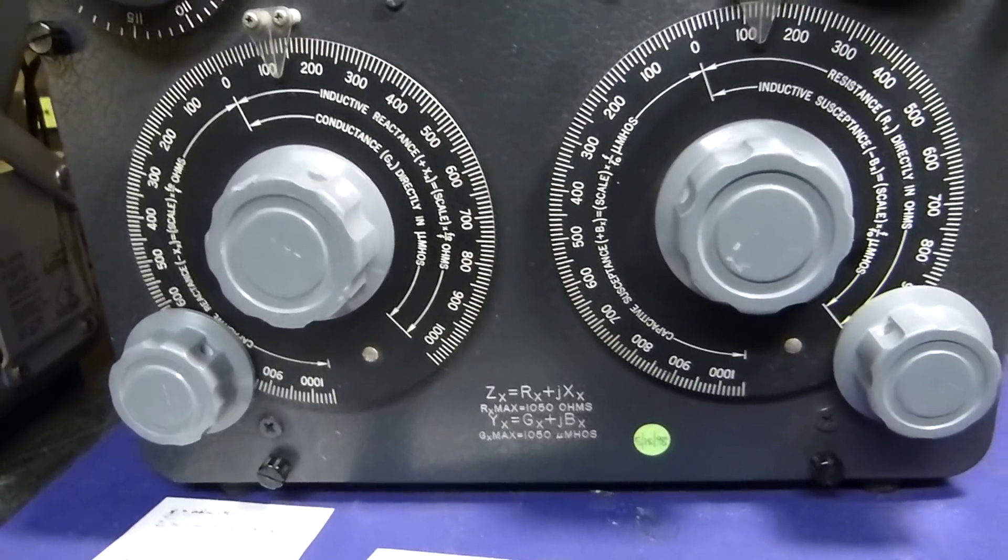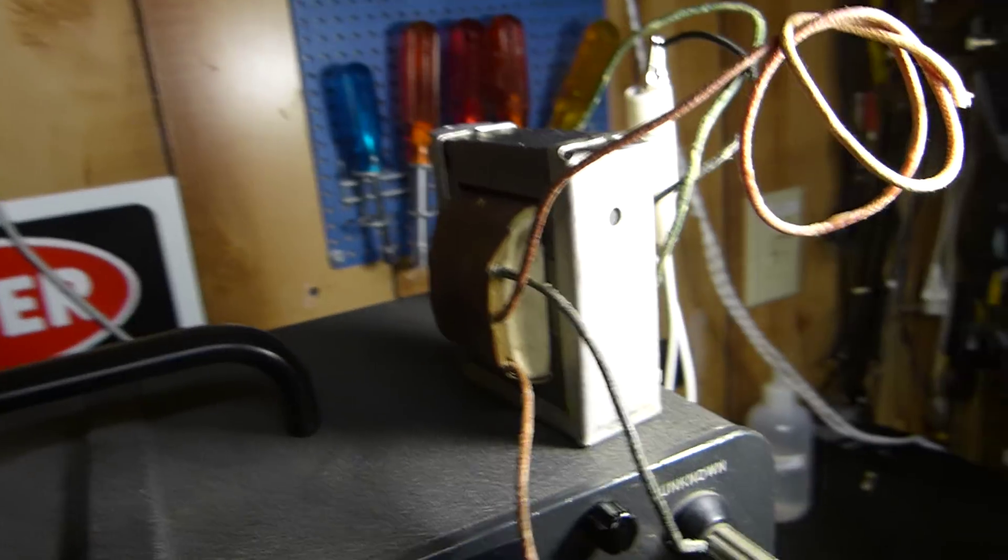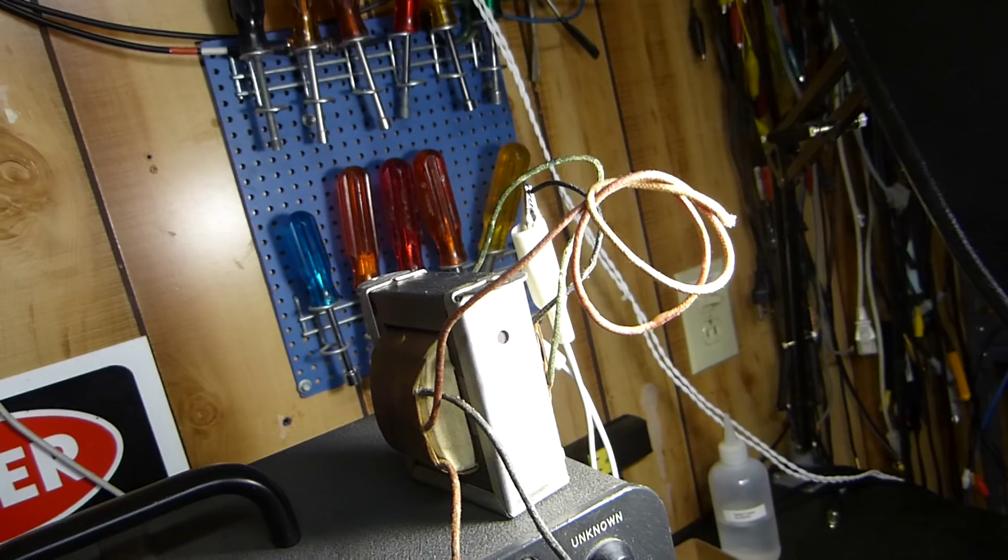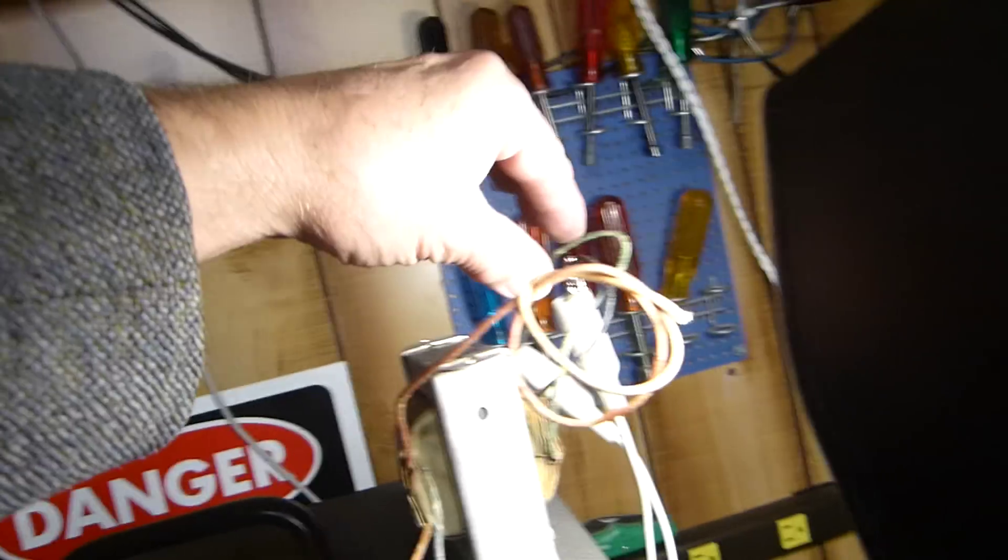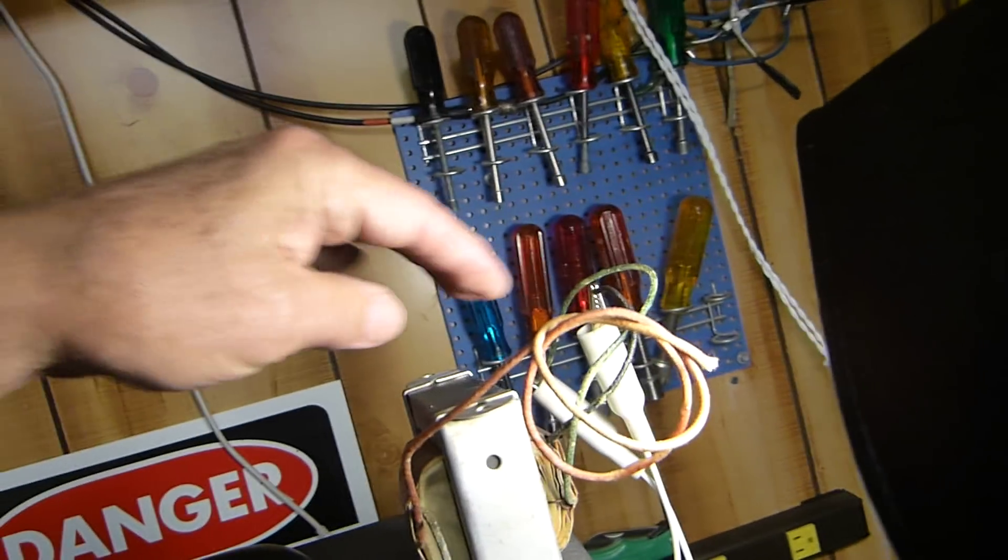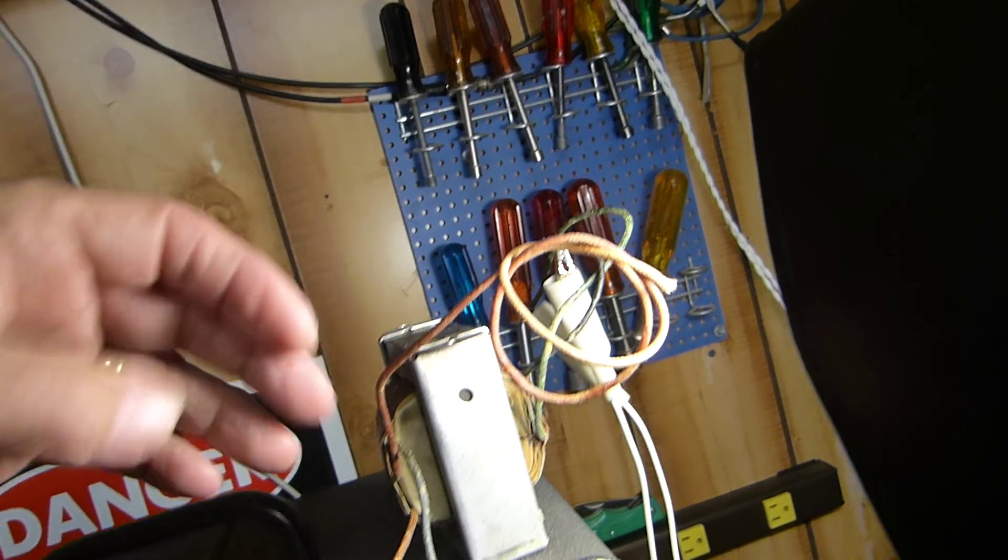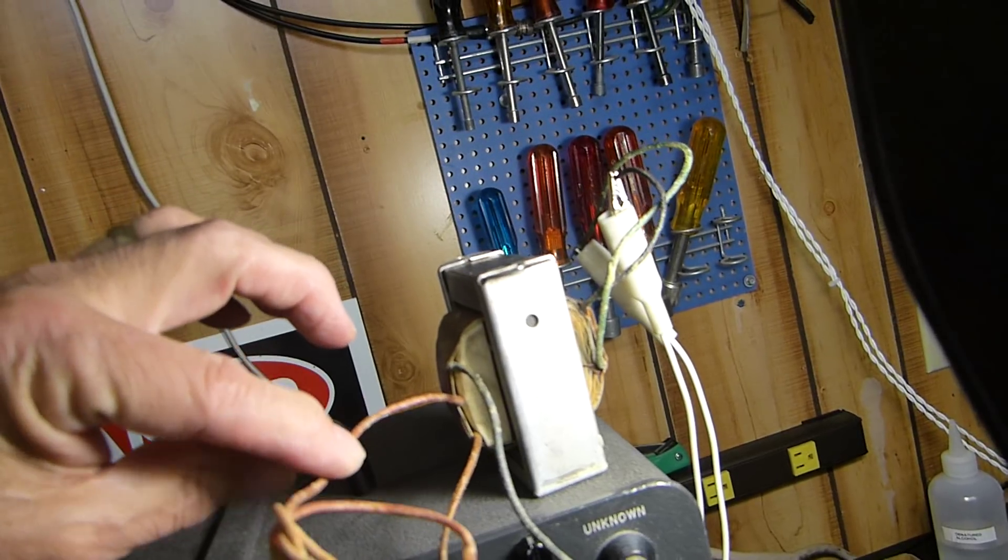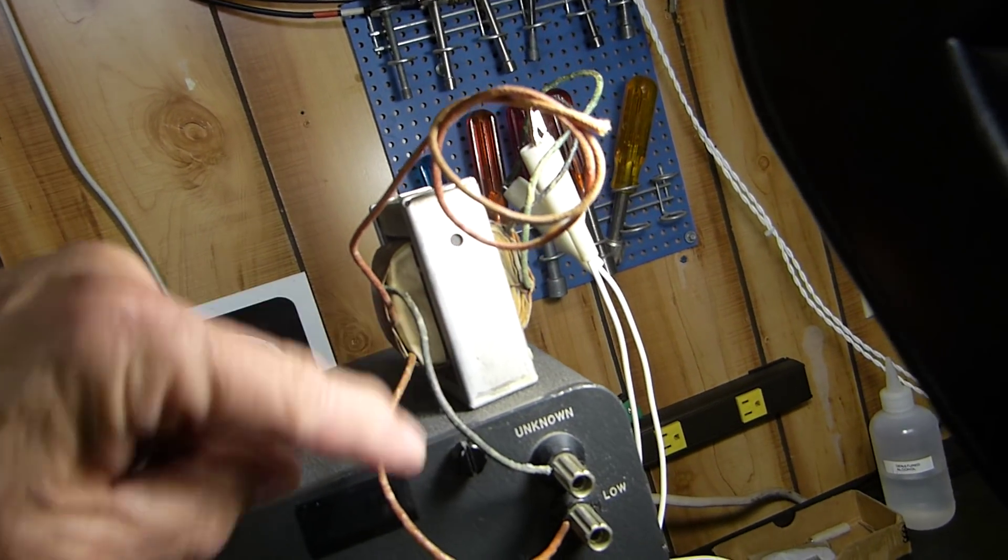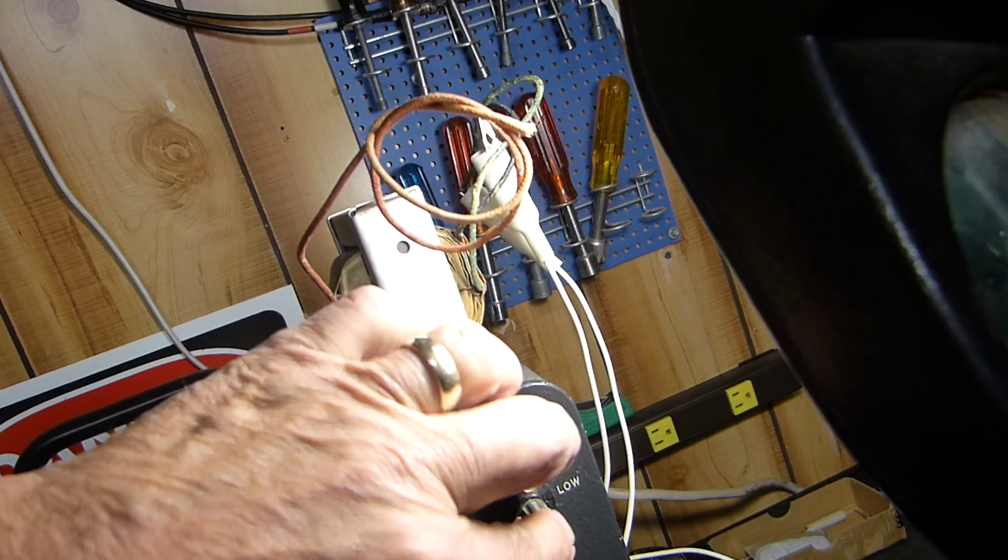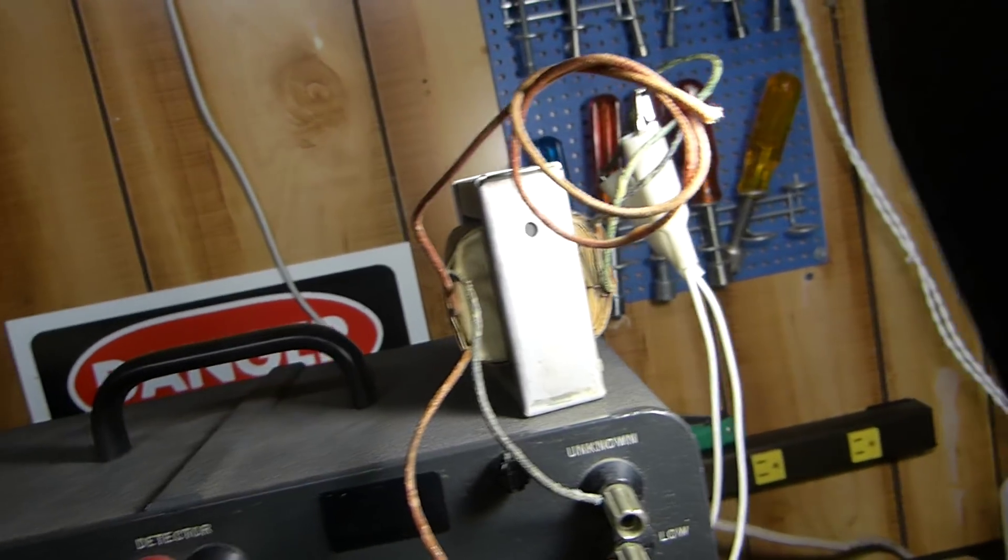I'm going to be using this transformer, a push-pull 6V6 transformer. Right now I've got eight ohms across the secondary. I've got the primary, this is the center tap we're not using. This would be a plate lead, this would be a plate lead. I've got it across the unknown and we're going to measure it.